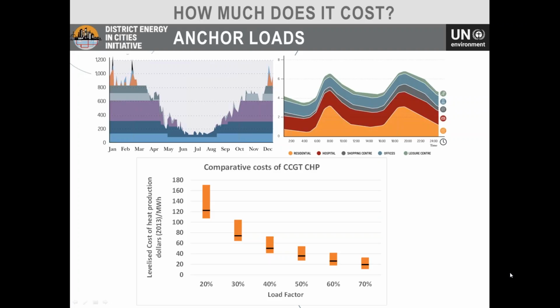In this case, it's also very important to have storage, so that if you're running CHP at only 20% of the year, you're going to have a much higher cost than if you combine it with storage, so that even when there's no heat demand, CHP can still provide load through storage as much as possible.